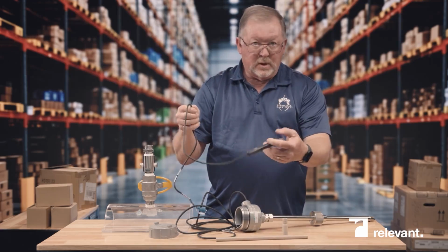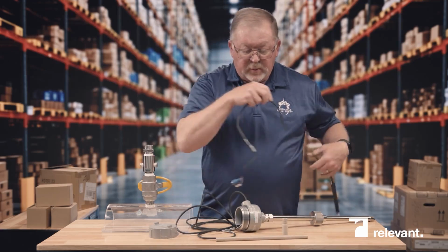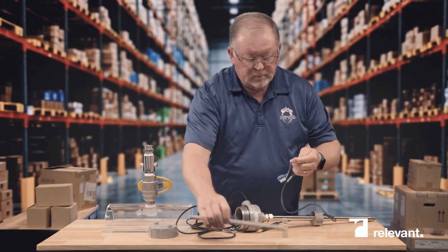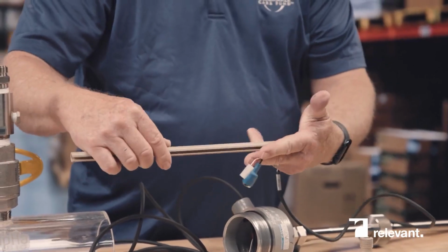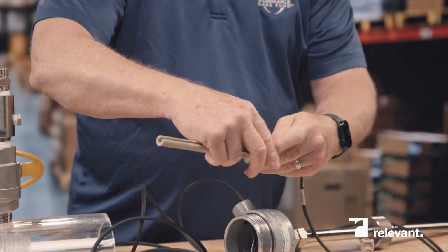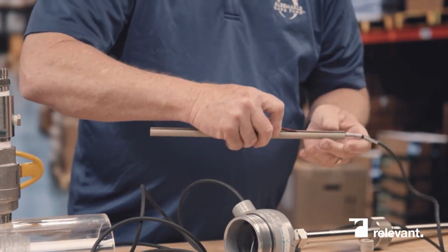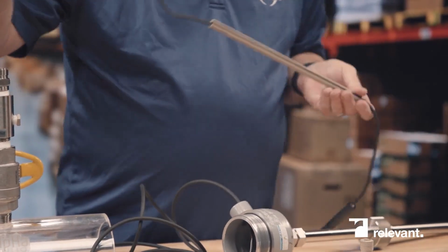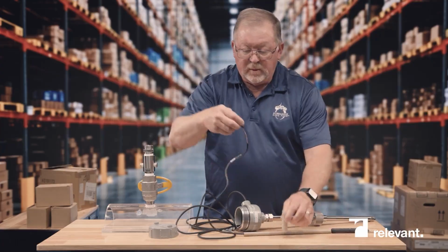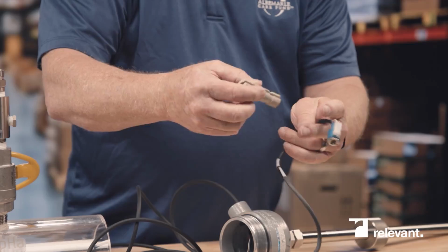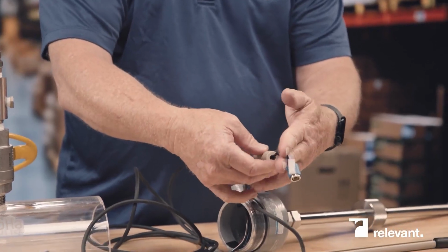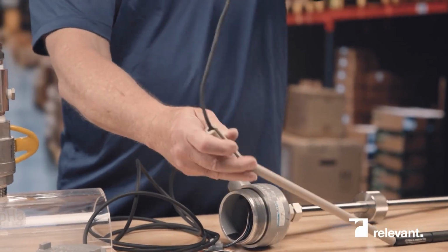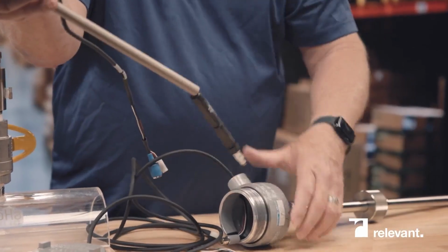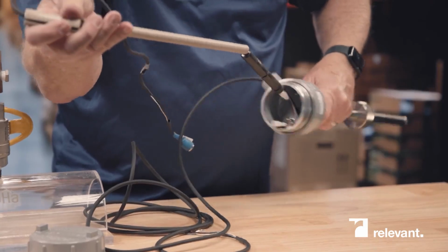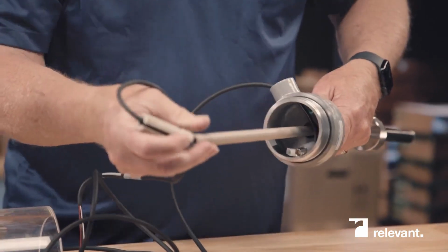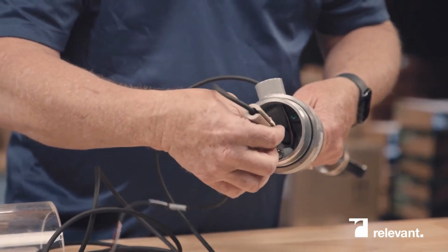Now you have your new pH probe in hand. You will reverse the process. If you install it this way, it's much easier. Same thing with the nut. Threads facing down, insert it into the slot, sliding it down the cable. Then we will reinstall back into the assembly. Use the spacer tube to press this in.